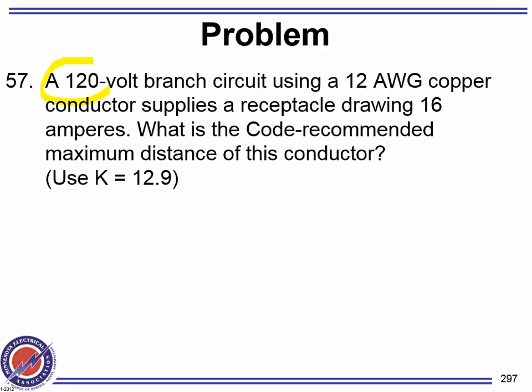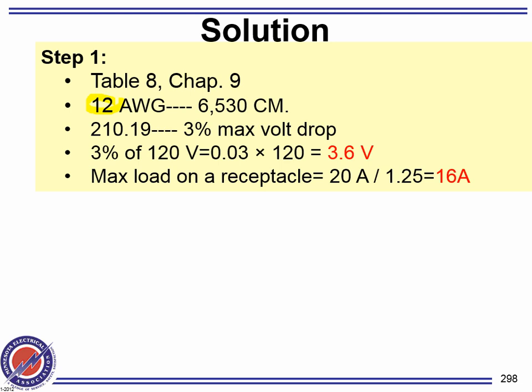Okay, I have 120 volts, number 12 conductor, 16 amps is the load. What is the recommended distance? How far can I pull the 16 amps? If I have a 16 amp load, I want to wire with number 12. How far can I put that load away from the panel? So is this a K or an R question first? It's a K. You need to flip it to find the distance. Okay, we just flipped it. Number 12, guys, from chapter 9, table 8, gives you 6530 circular mil. Voltage drop is 3%. In order to put the voltage drop in the formula, guys, you must convert the voltage drop from a percentage into actual volts. So 3% of 120 is how much?